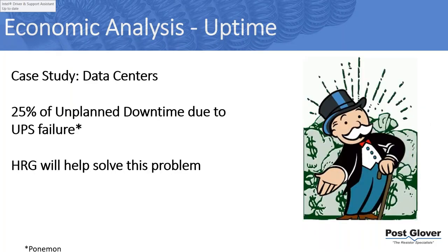So just to continue that real quick, in terms of data centers, I wanted to say that, look, this is not always good. A high resistance ground can't help with all of this downtime. You have hacking, you have a lot of different reasons, software failure, even some hardware failure that's not power related. There's things that can happen that high resistance ground can't do anything about. But the point is that a large percentage of that it can, and that's what that 25% is essentially.